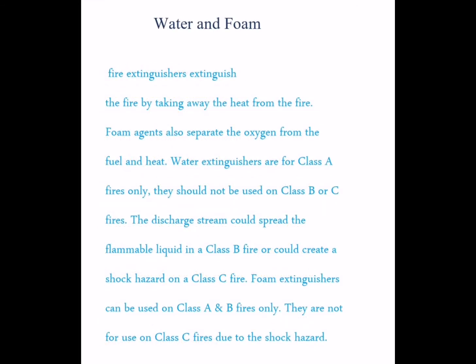Water and foam. Water and foam fire extinguishers extinguish the fire by taking away the heat from the fire. The foam agents also separate the oxygen from the fuel and heat. Water extinguishers are for Class A fires only. They should not be used on Class B and Class C fires.